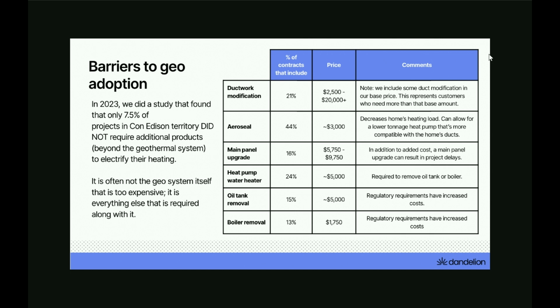So this is reflective of installations in Con Edison territory because it was the data that I had on hand when I was asked to make this presentation, but it's pretty representative of the Northeast market that we serve. So the key takeaway here is really that only 7.5% of the projects that we install just need a heat pump. So 7.5%, cut the old one out, slide the new one in, and walk away. But most everybody else needs some kind of infrastructural improvement to actually make the heat pump work as it should, or at the rated efficiencies that we're desiring.